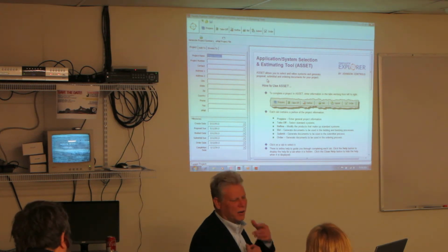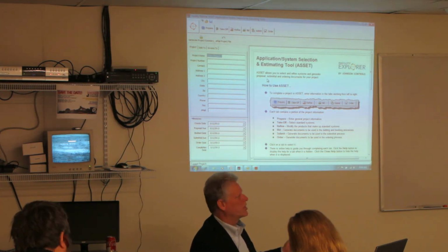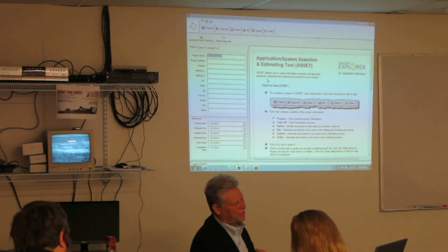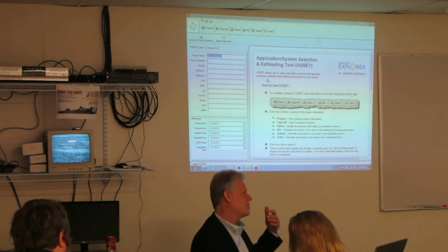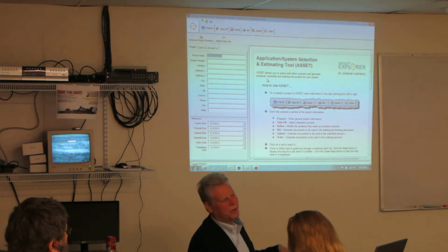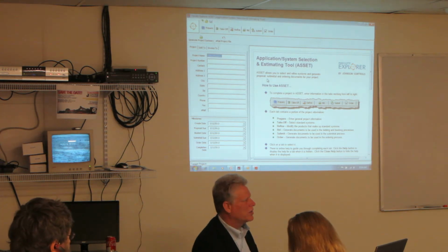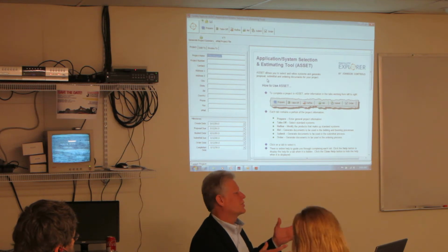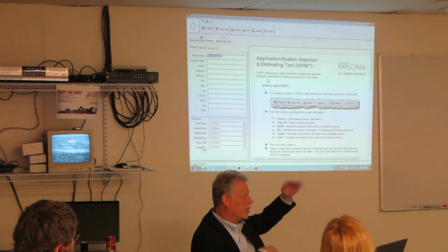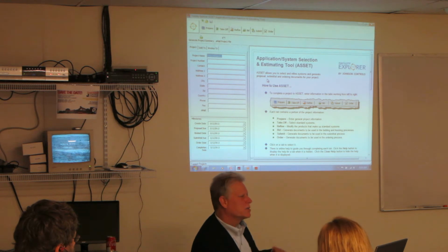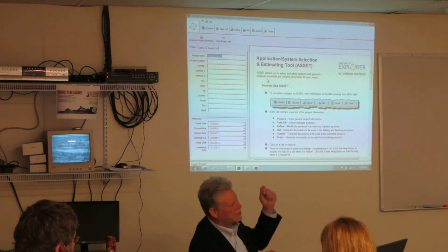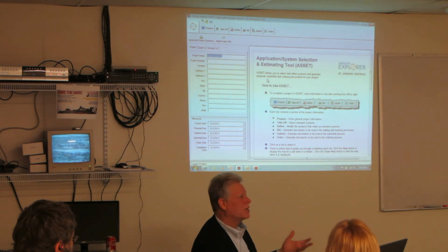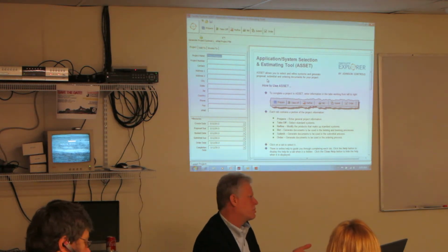real quick, a lot of times someone calls in, or you went out and looked at the job site and you're sitting down writing all your notes down: outside air temp and return temp on this air handler, and mixed air dampers and VFDs, and you're writing all those things down, which is great. But if you don't know your controllers and how many points there are on a controller, next thing you know, you're saying to yourself, well, I got 6 analog inputs on this controller, I'm writing all these things down, and if you miss any of those things, you kind of missed your bid.